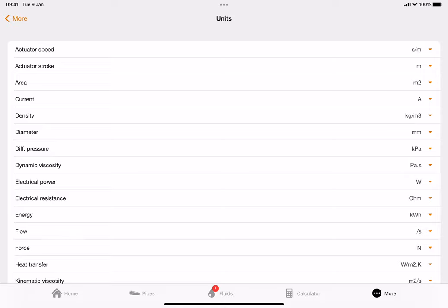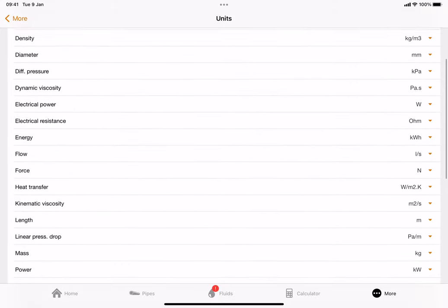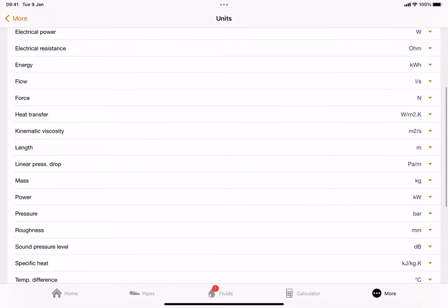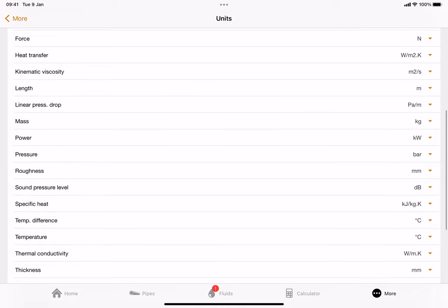We do need heat transfer in watts per meter squared Kelvin. Length is important - we want that in meters, shown as 'M' on the screen. The next one, also very important because we're working with pressure drops for pipe sizing, we need that in pascals per meter - PA/M as you can see on the screen. Mass in kilograms, power in kilowatts, pressure we want in bar.